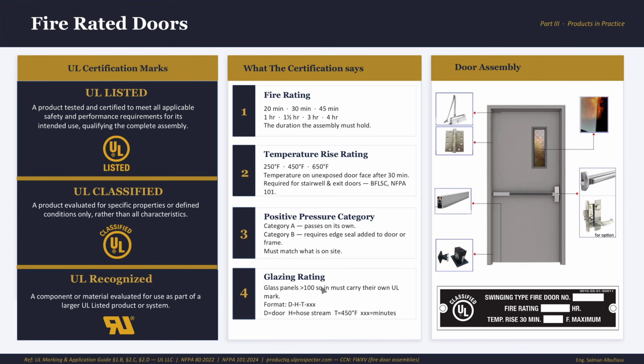And then glazing ratings. Any glass panel over 100 square inches must carry its own rating. Why? Because let's say this glass is 45 minutes and the door is 90 minutes. That means the entire door will be 45 minutes and not 90 minutes. The weakest element sets the rating. The weakest element from all of these or any of these will be the rating of the door.